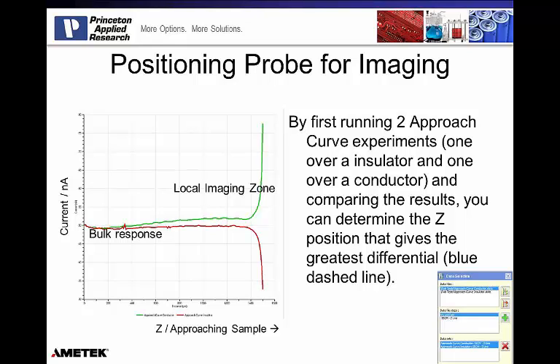But as I start bringing the probe closer and closer to the sample surface, and you can see this grid line right here is 1,400 microns, if I was to position it at 1,400 microns, closer to the sample surface, we can see that I would be getting approximately a 48 nanoamp response out of an insulator and about a 51, 52 nanoamp response out of the conductor. So while that's appreciable and statistically significant, it's only about a 4% difference from the bulk of these two responses.